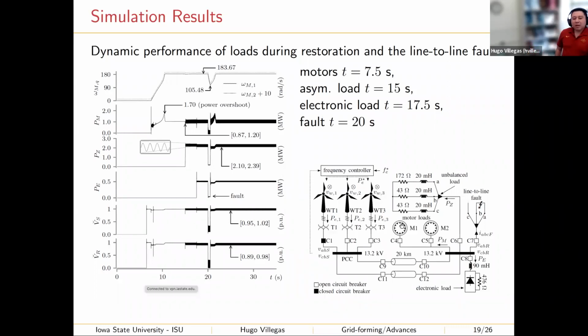So then I came to the conclusion that we have to be careful when we are designing these grid forming controllers. We need to make sure that, for example, several units in parallel are going to be able to remain in synchronism. Because what happened is when the motors were reaching this point, voltage and speed regulation was challenged, and then the turbines went out of sync. So it was challenging. I was sad at that because I thought I already had a prototype that was working, and then I tested with another turbine in parallel, and it didn't work.